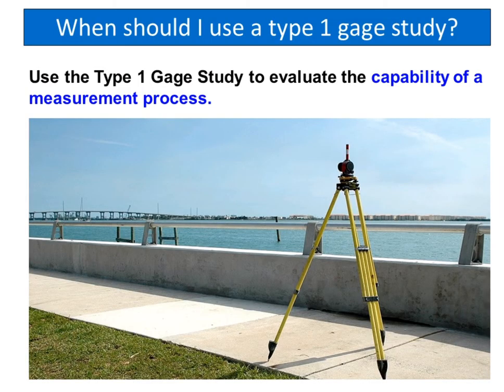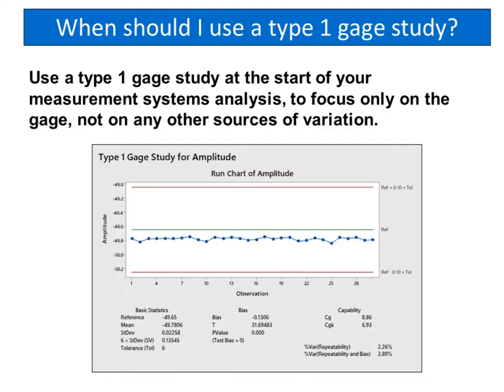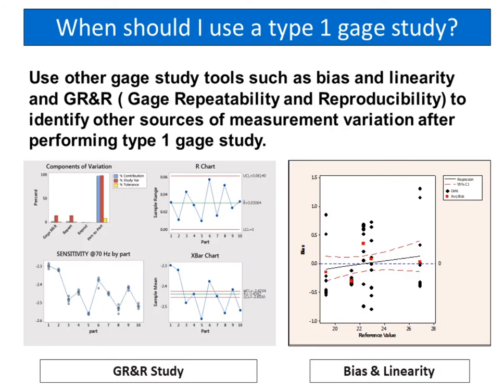When should you use a type 1 gauge study? Use it to evaluate the capability of a measurement process, specifically at the start of your measurement systems analysis to focus only on the gauge, not on any other sources of variation. Use other gauge study tools such as bias and linearity and GR&R — gauge repeatability and reproducibility — to identify other sources of measurement variation after performing a type 1 gauge study.